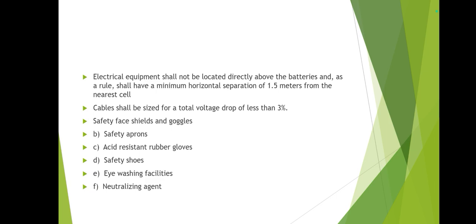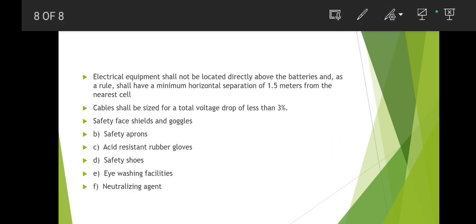Cable shall be sized for a total voltage drop of three percent losses. Inside the battery room, there should also be a safety box containing: safety face shield, goggles, safety aprons, acid-resistant rubber gloves, safety shoes, eye washing facility, and a neutralizing agent. A drain system should also be present.